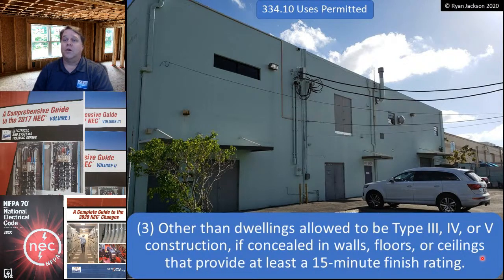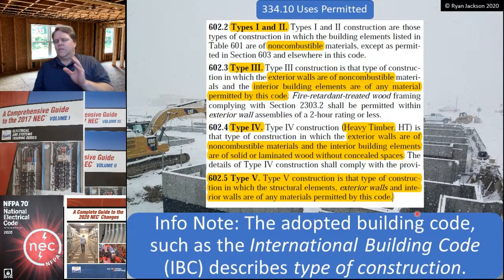You cannot have it exposed in other than dwelling units, and you can't have it at all in Type 1 or 2 construction. There's an informational note that says the adopted building code, like the IBC, describes type of construction. I took a screenshot from my own code book and showed you what I highlighted. Really, what you need to know is that types 1 and 2 are completely non-combustible. That's your walls, your roof, your floor-ceiling assembly, not just the structural members like the exterior walls, but all the partitions and everything else.